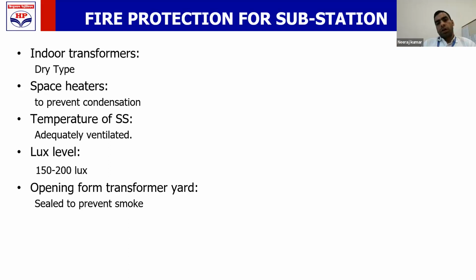Openings from the transformer yard to the substations shall be sealed so that the smoke, when there is a fire in the transformer yard, does not travel to the substation. This is also important from the point of view of propagation of fire through openings. So you should ensure that your transformer and your substations, even though located side by side, are isolated from the point of view of fire propagation or smoke entry. That is why all openings from the transformer side are sealed. This point will be further discussed in the transformer fire protection section.